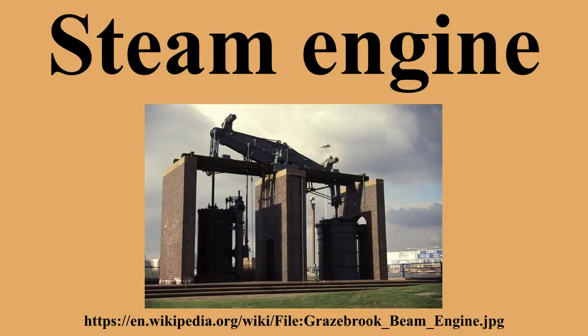Water pump. The Rankine cycle and most practical steam engines have a water pump to recycle or top up the boiler water, so that they may be run continuously. Utility and industrial boilers commonly use multi-stage centrifugal pumps. However, other types are used. Another means of supplying lower pressure boiler feed water is an injector, which uses a steam jet usually supplied from the boiler. Injectors became popular in the 1850s but are no longer widely used, except in applications such as steam locomotives. It is the pressurization of the water that circulates through the steam boiler that allows the water to be raised to temperatures well above 100 degrees Celsius, the boiling point of water at one atmospheric pressure, and by that means to increase the efficiency of the steam cycle.